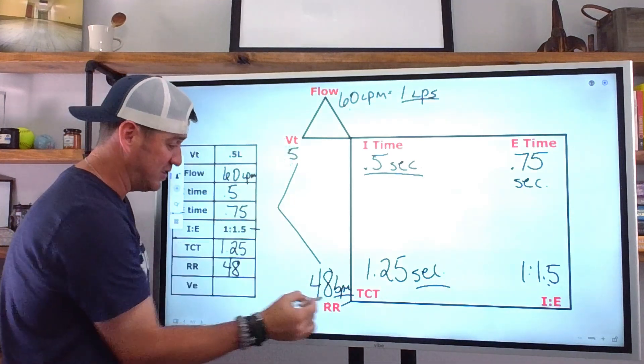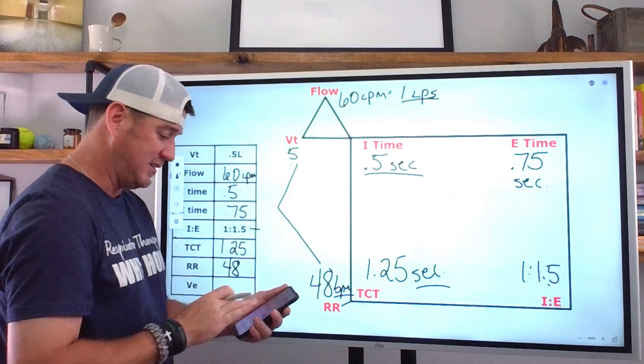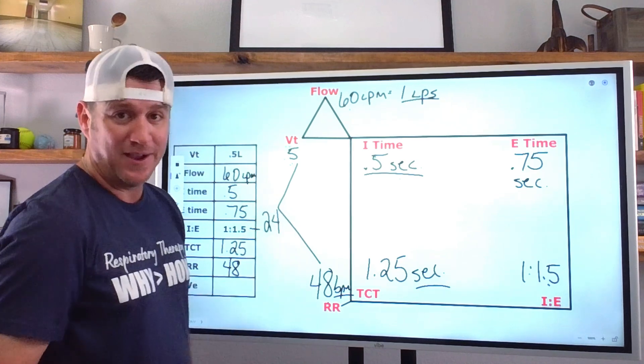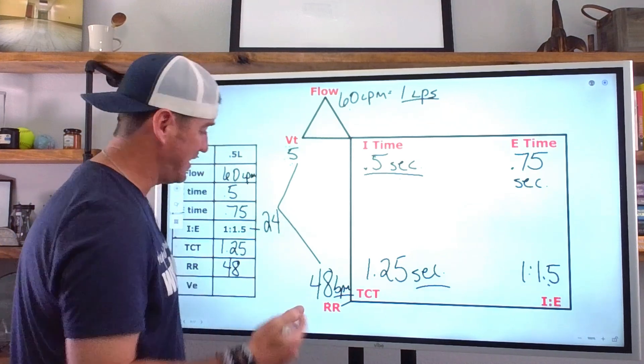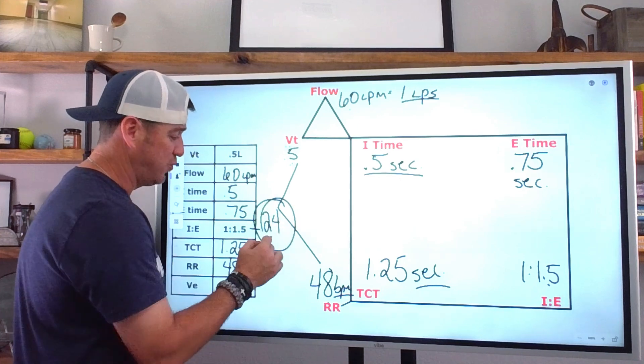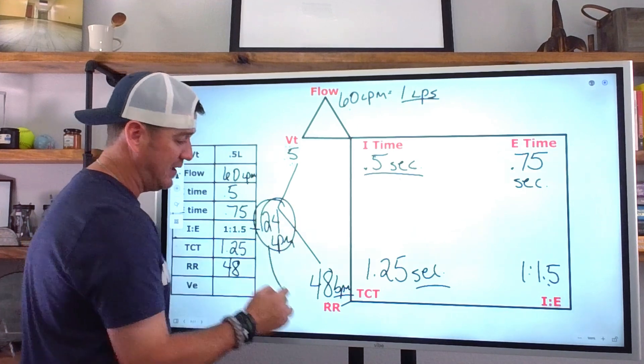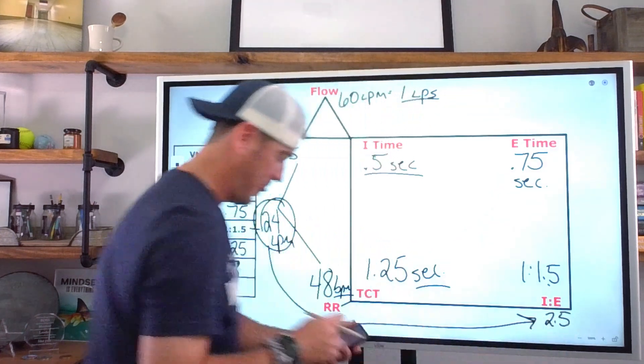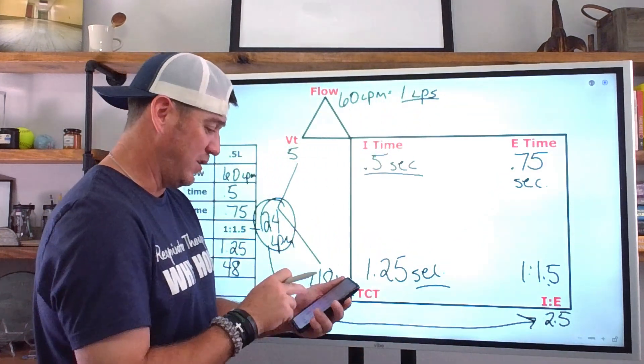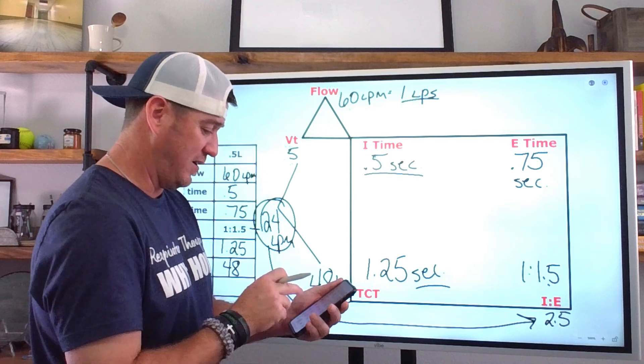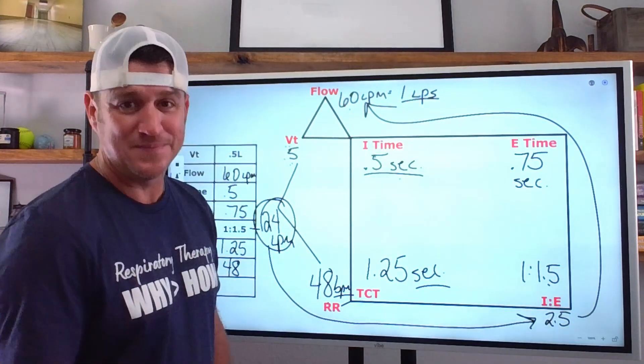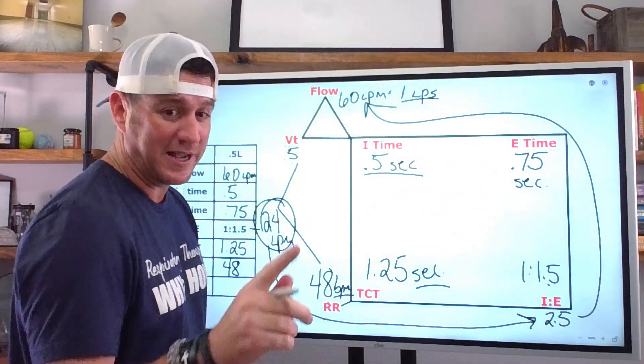We can now get our minute volume. Tidal volume times respiratory rate: 48 times 0.5 equals 24 liters per minute. And to check: 24 liters per minute times our total parts of 2.5 equals 60 liters per minute. That's how you do it.